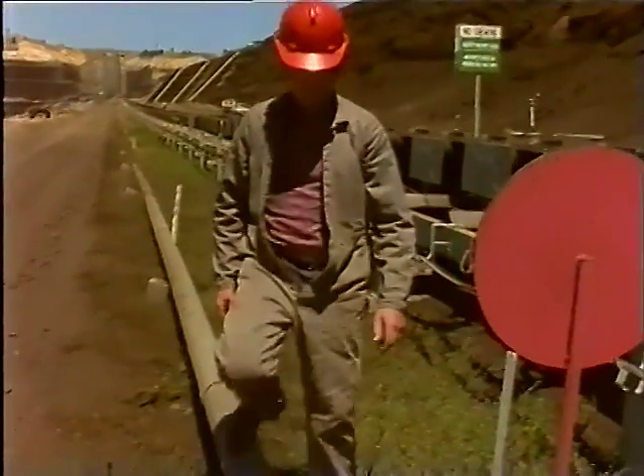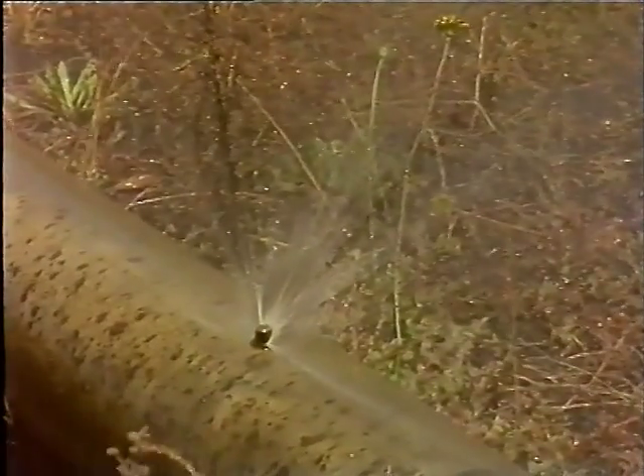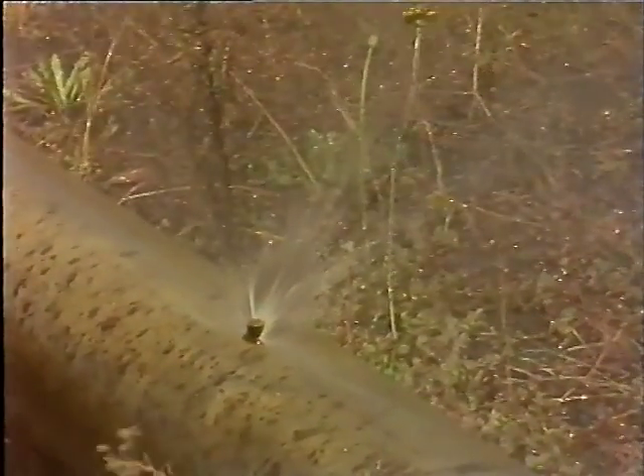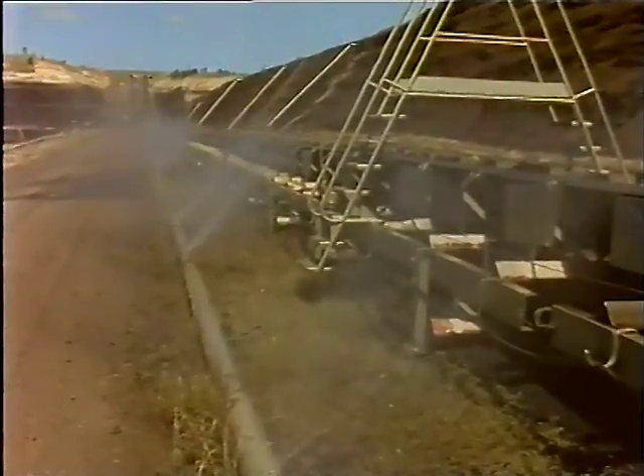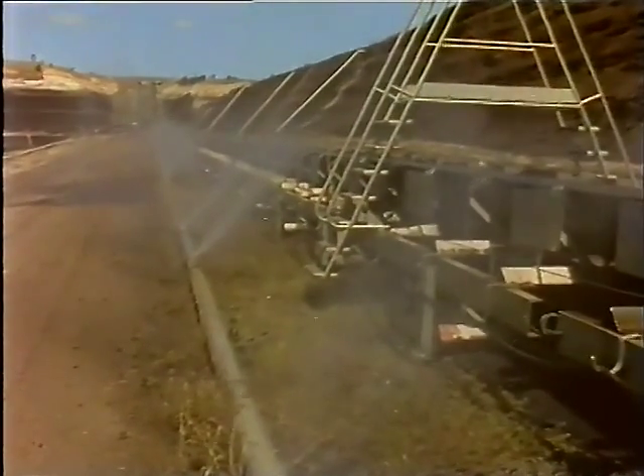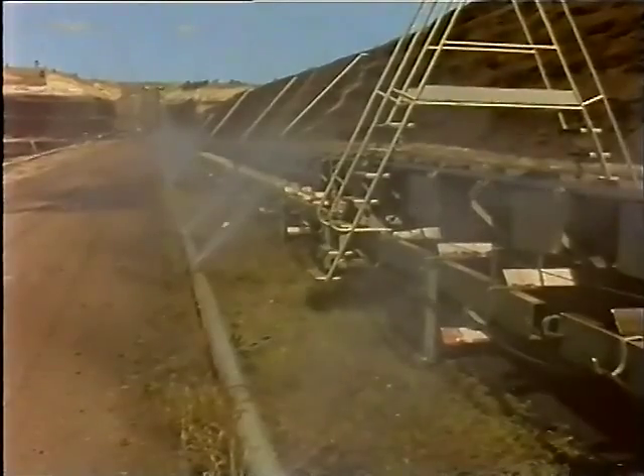Control valves for bird's mouth sprays are located at regular intervals along the conveyor. Remember: in case of a hot idler, do not turn off the conveyor belt, as this increases the risk of fire. Not all fires on conveyors are caused by hot idlers, so determine the cause and effect of the fire before you act.